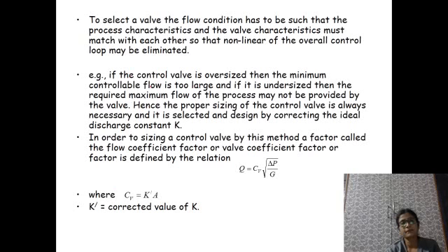If the control valve is oversized, then the minimum controllable flow is too large. Oversized means the valve sizing is more, and the minimum controllable flow is too large. If it is undersized, then the required maximum flow may not be provided by the valve.